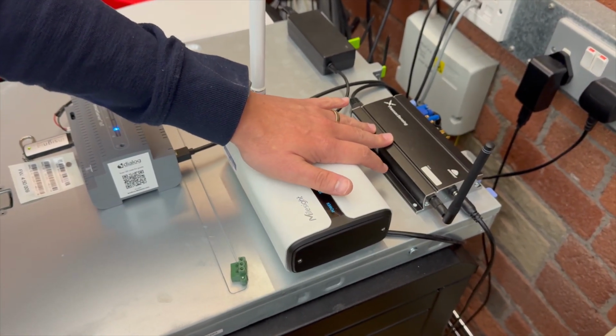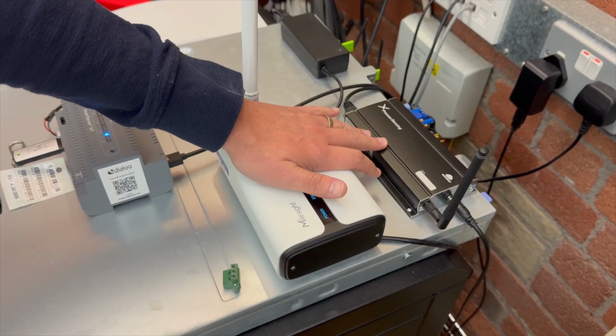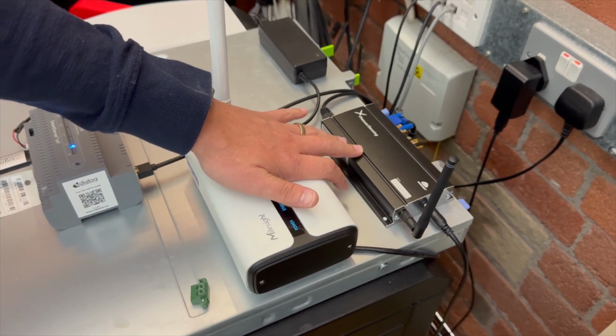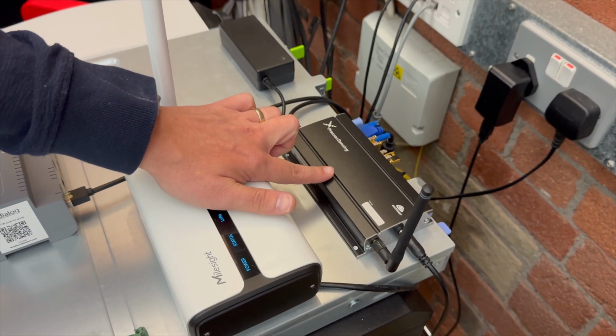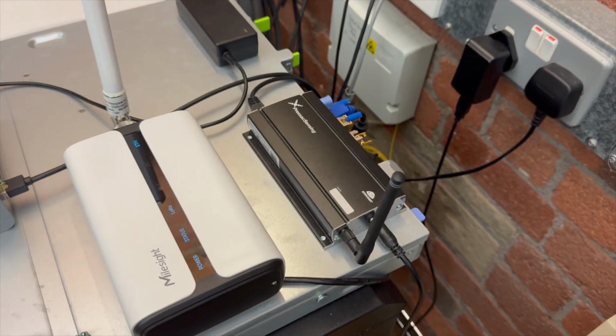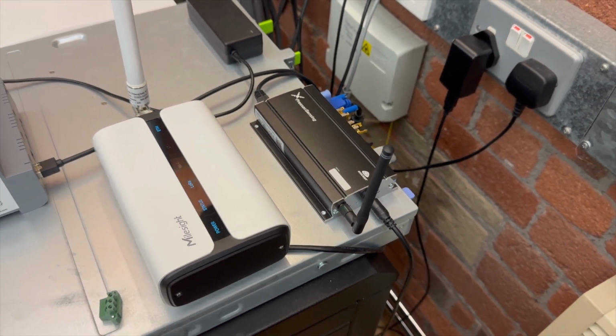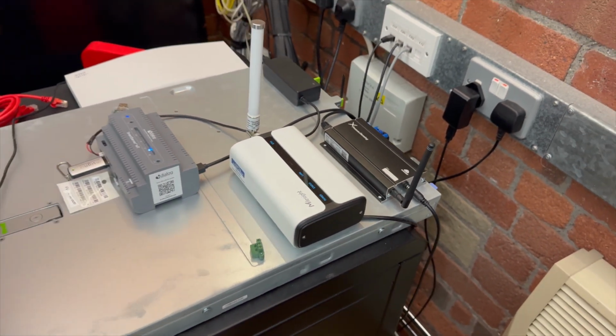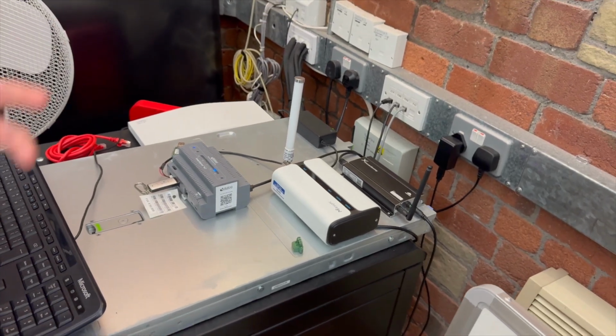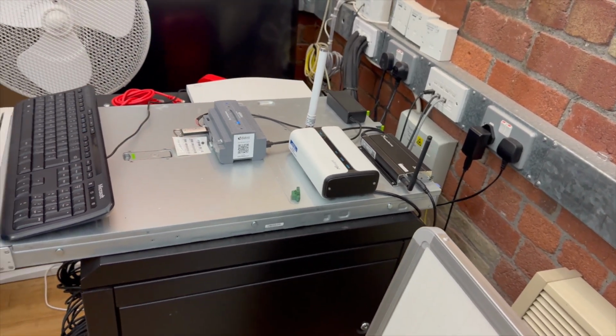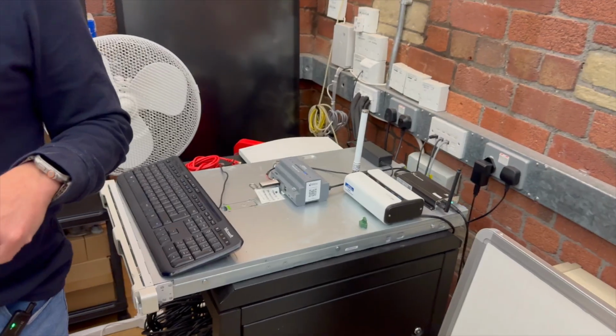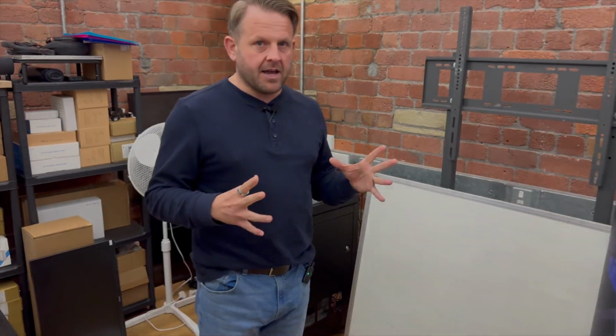This is the one that, if you're not using the gateway inside the access points, you will need to have one of these, if not one per floor, and then every 30 meters you need to put a repeater to boost the signal to that device. If you remember, that's because it is low powered and requires more of a signal, whereas LoRaWAN will run for kilometers in that area.